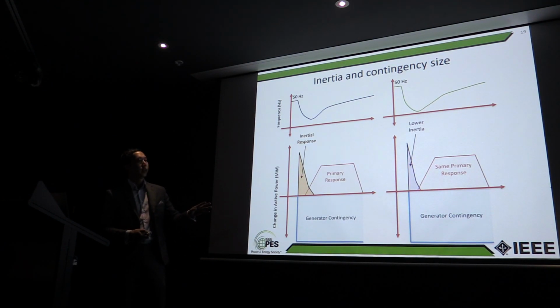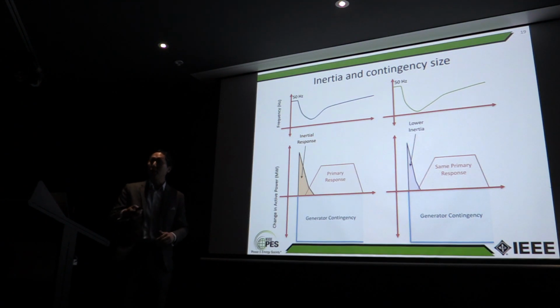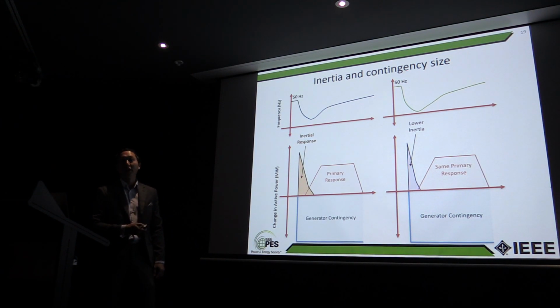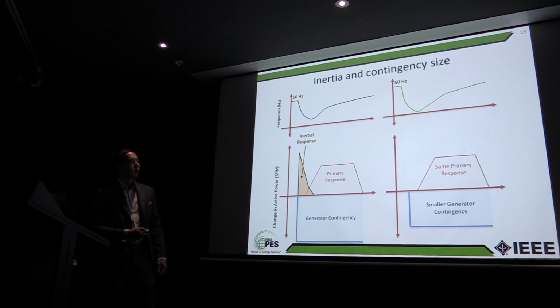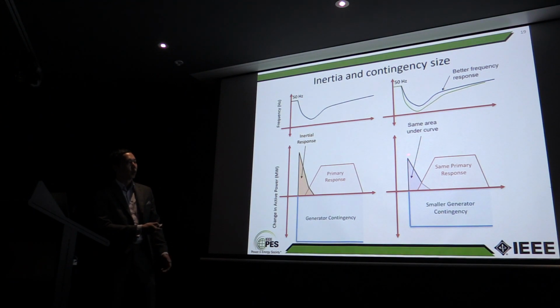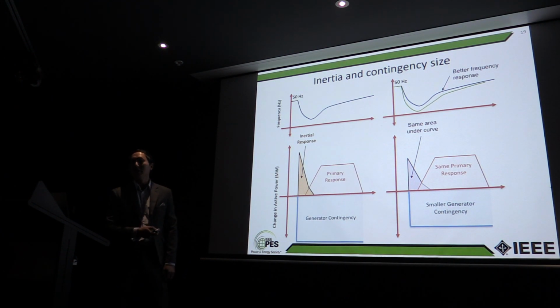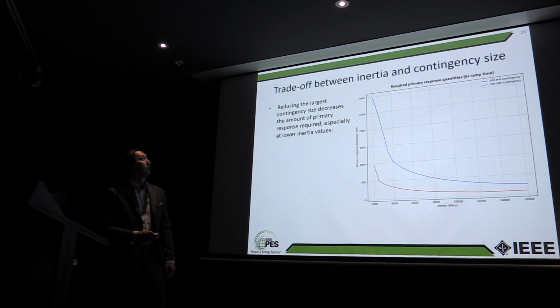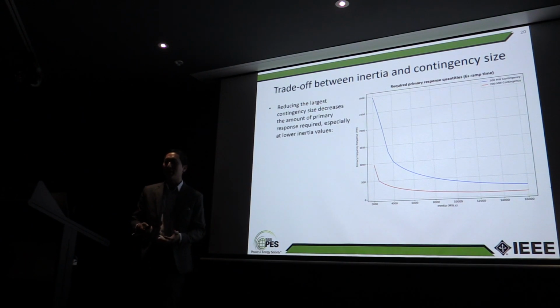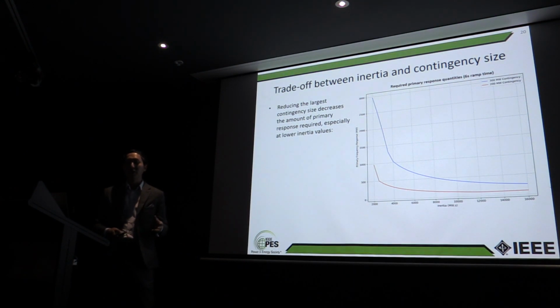So the other thing I want to say, so we talked about the inertia ramp, the primary response ramp time and the quantity. The next thing I want to talk about is how inertia and contingency size are affected. So we've gone back to the same picture again. We have lower inertia, but rather than having that contingency size here, we have a smaller one. And so this is the same inertia, but because it doesn't require this, it requires less power to recover in the first instance. That area under the curve is the same, but you get more of it over time, and so you have a better frequency response. So the conclusion there is that there's a trade-off between inertia and contingency size. So you can lower your contingency size at lower inertias to give you better response with the same amount of primary response that you have, all things being equal.